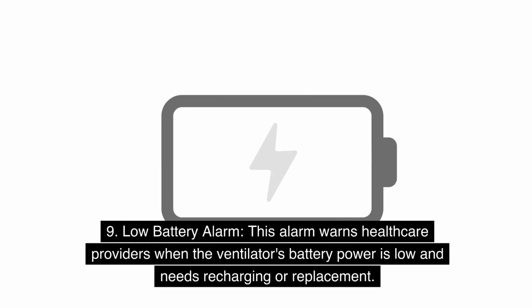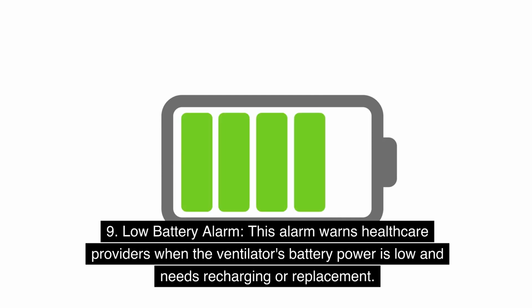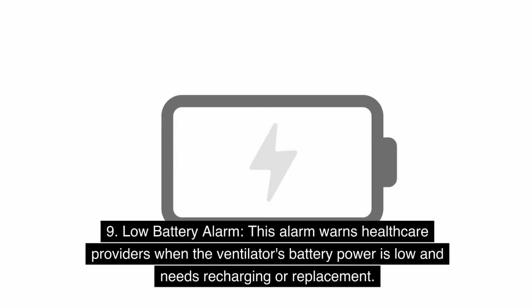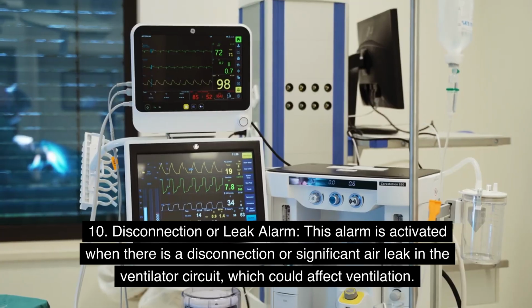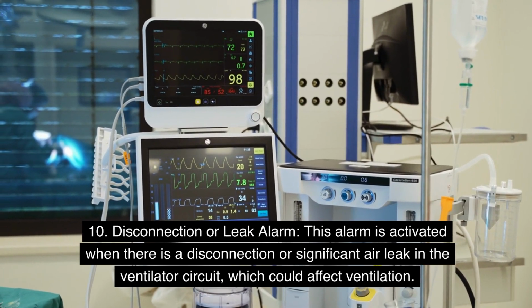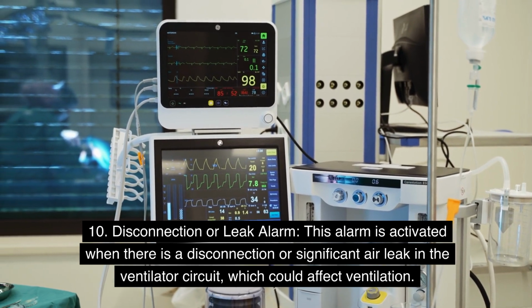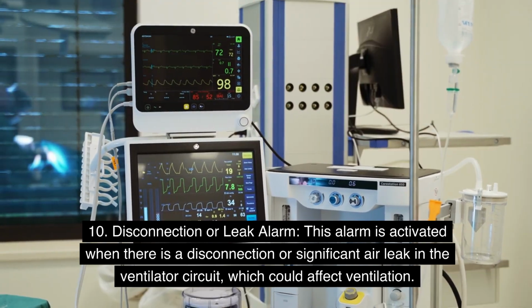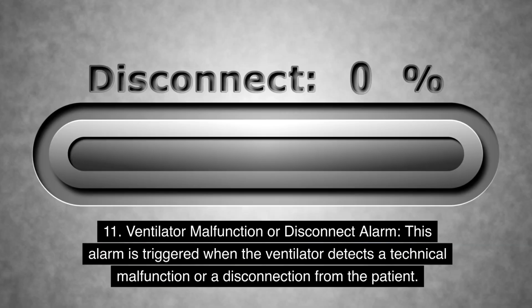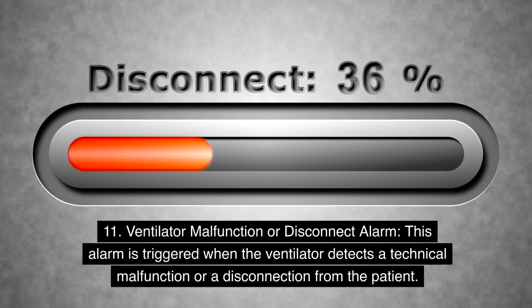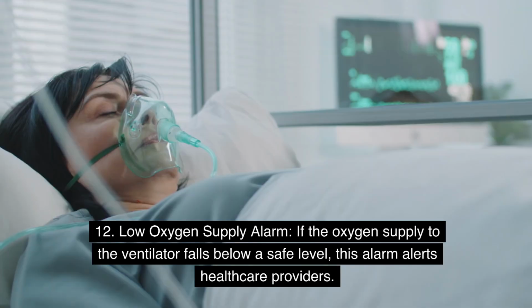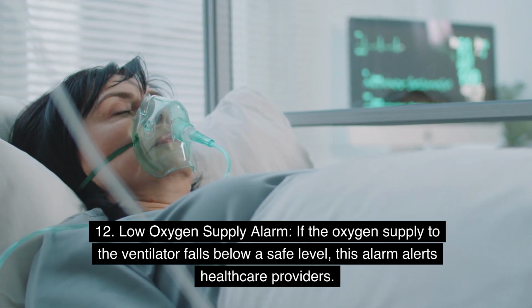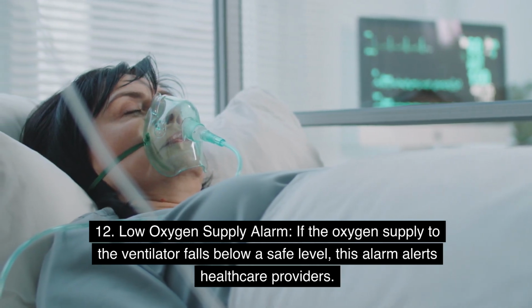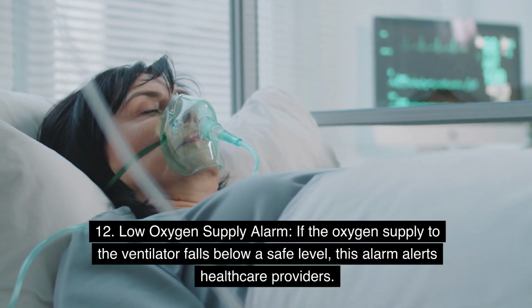9. Low battery alarm. This alarm warns healthcare providers when the ventilator's battery power is low and needs recharging or replacement. 10. Disconnection or leak alarm. This alarm is activated when there is a disconnection or significant air leak in the ventilator circuit, which could affect ventilation. 11. Ventilator malfunction or disconnect alarm. This alarm is triggered when the ventilator detects a technical malfunction or a disconnection from the patient. 12. Low oxygen supply alarm. If the oxygen supply to the ventilator falls below a safe level, this alarm alerts healthcare providers.